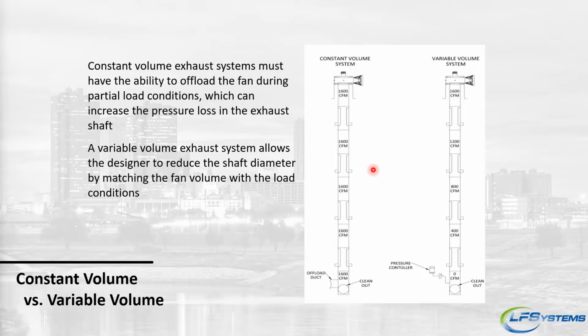But the problem with that is this fan is now running, in this example, 1600 CFM, the entire length of the shaft. And if it's 2 in the morning and no one's doing laundry, that air has to come from somewhere. It will draw through these openings a little, but you have to have some kind of a relief damper or an offload damper so that you're pulling in that 1600 CFM to make sure that you don't draw this into a vacuum. What typically ends up happening is this duct is in a conditioned space. So now you're drawing conditioned air right up that duct, all the way up and out through the building. And in this scenario, it's 1600 CFM.